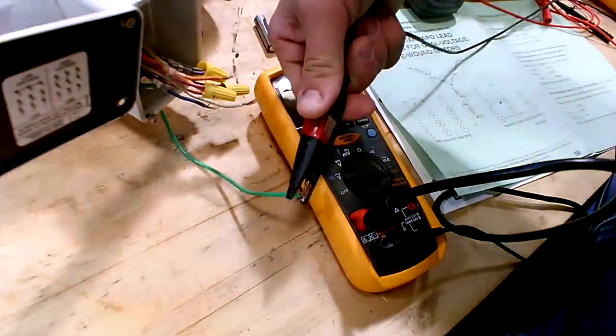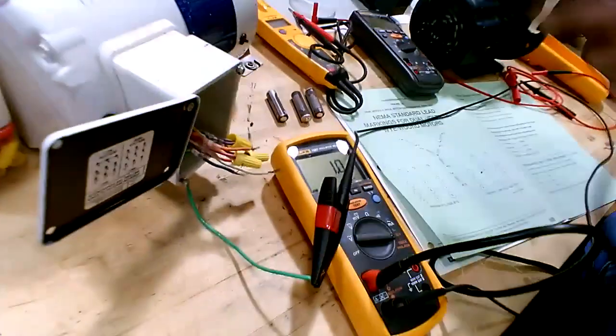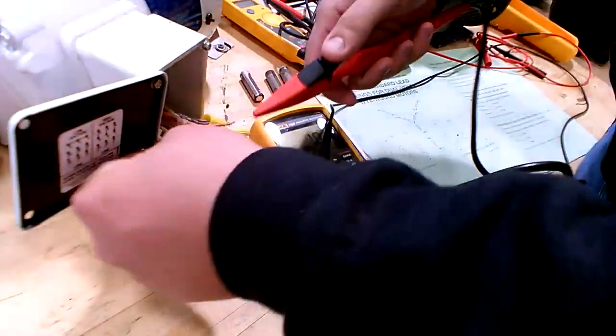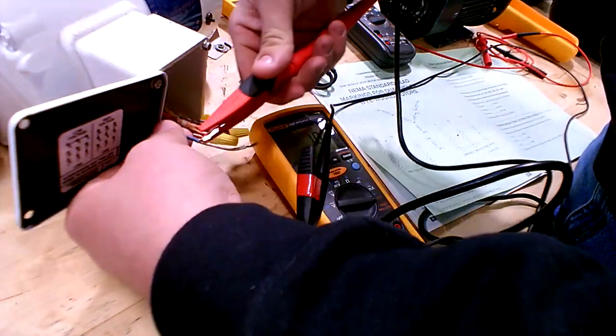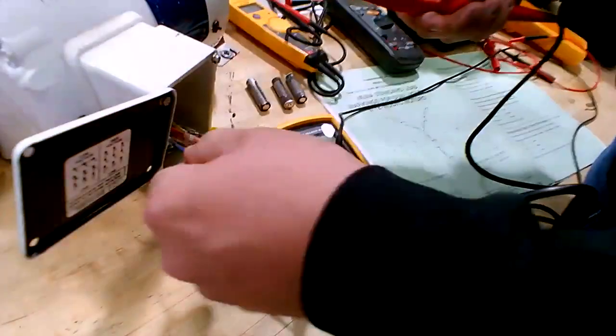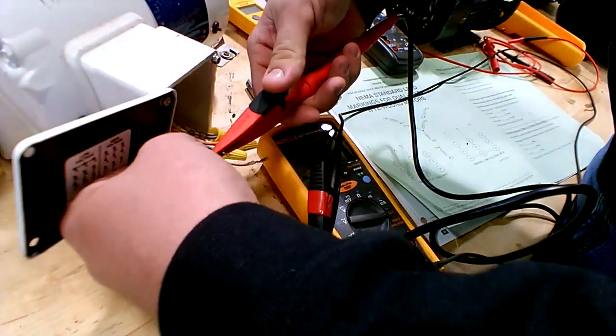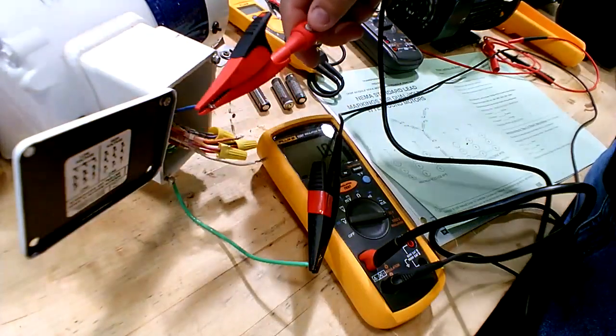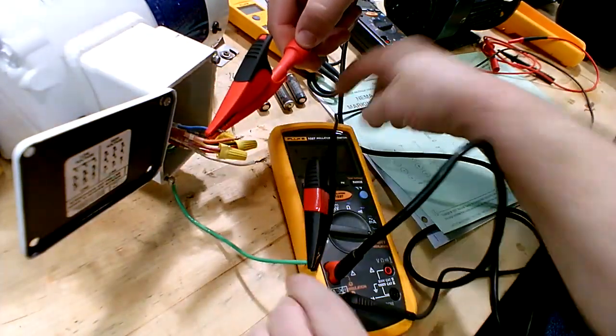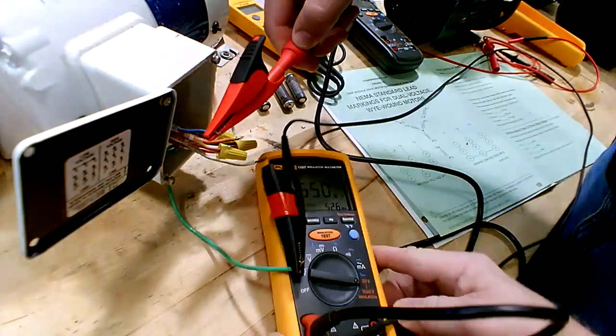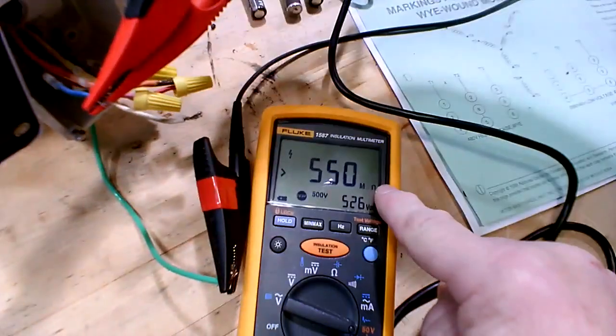Okay, so hook it up, each leg to ground. And you make sure that the other leads don't hit anything, or it's just going to throw the reads off. Okay, so you're doing that, he's going to hit the button, and we're going to get a reading here. And what does it say? It says greater than 550 megohm. So that's the highest reading it can read.